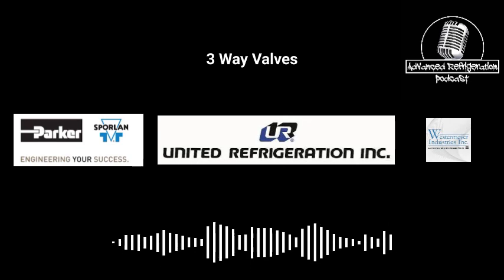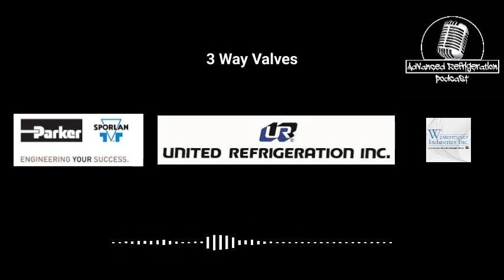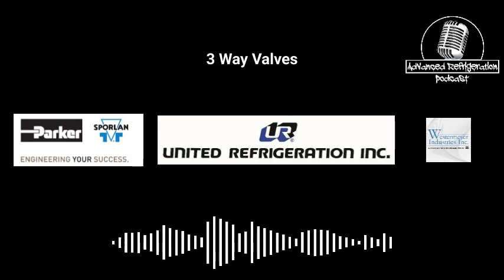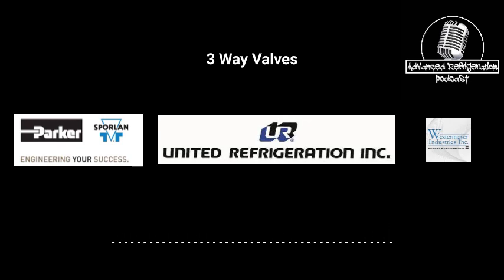If you walk up to a stuck three-way valve that's stuck in between, you can hear it ripping through both ports. It sounds like a river flowing through because it's just high pressure gas going around both sides, and neither one of them is getting good flow.